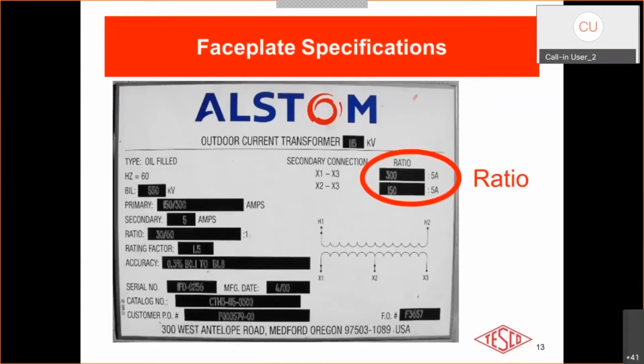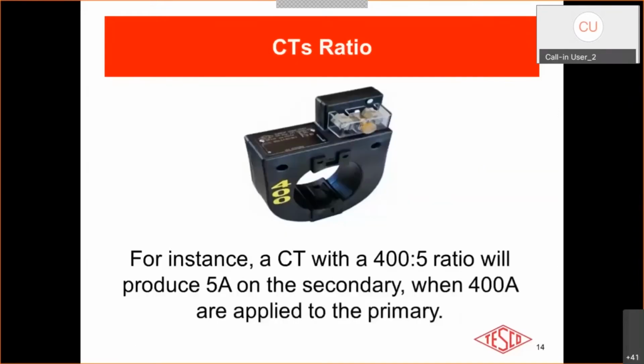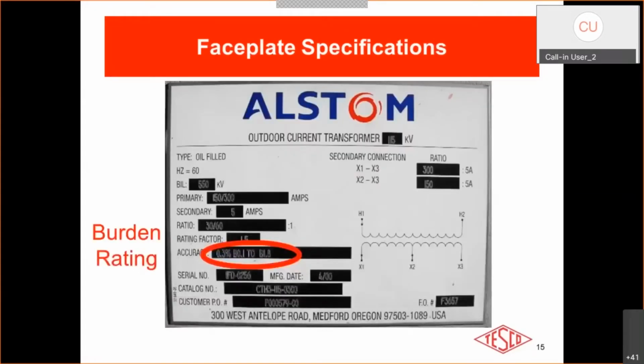You will have a ratio specification. A ratio, for instance, using this example, a 400:5 ratio will produce 5 amps on the secondary when 400 amps are applied to the primary. You will also have a burden rating as well. In this example here, it's kind of hard to read, but on this faceplate, it says 0.3% at burdens of 0.1 to burdens of 1.8.